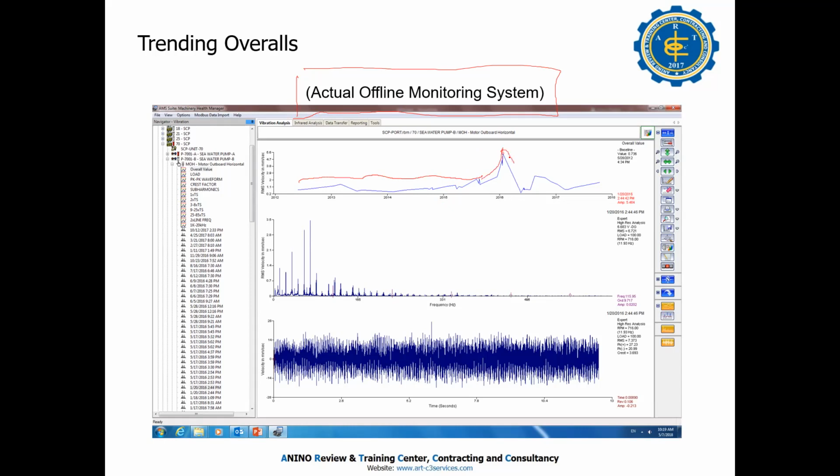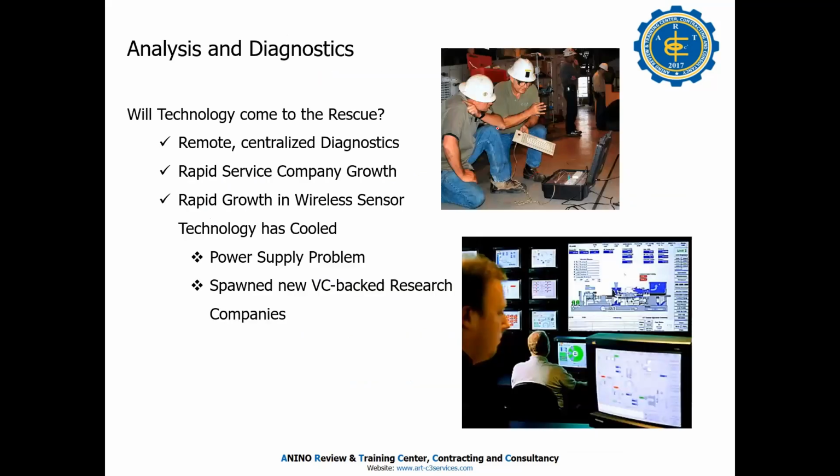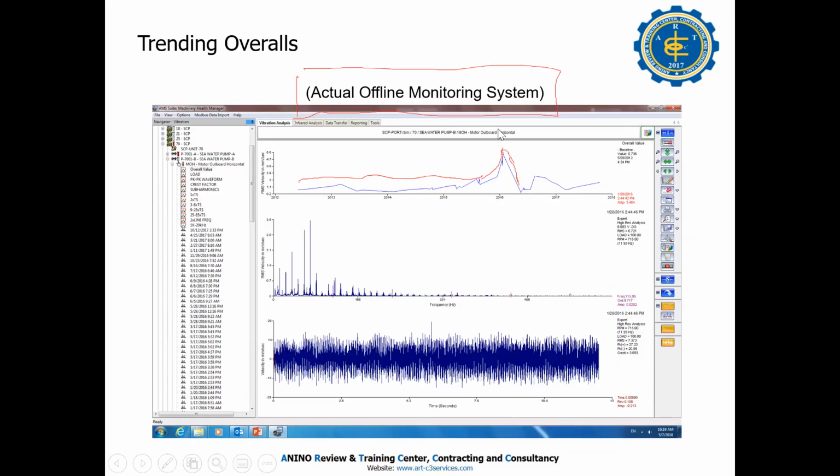Then we only changed the bearing, and the vibration went down. So that's the good thing about the software: we can track the time. When we go to the management, it's here.